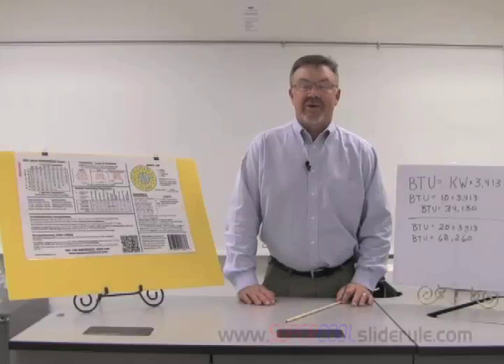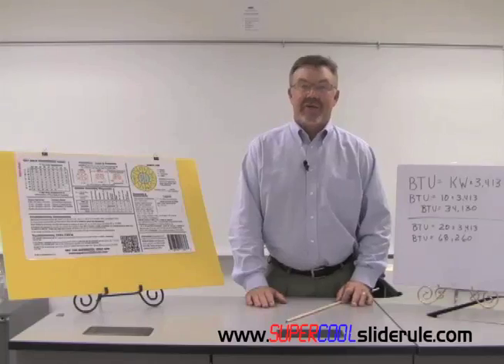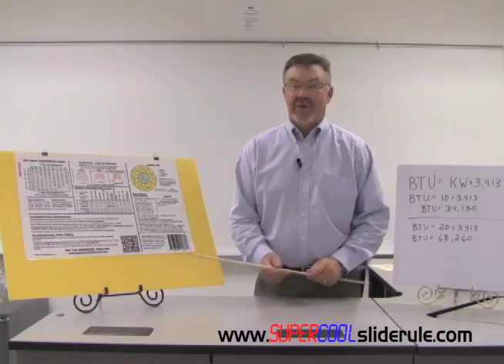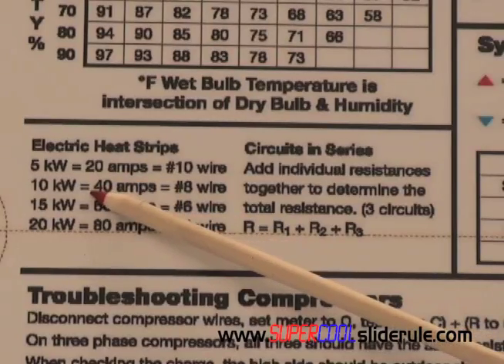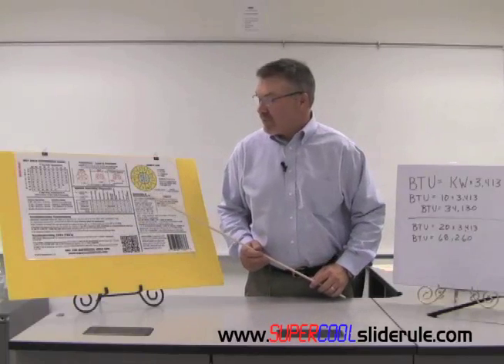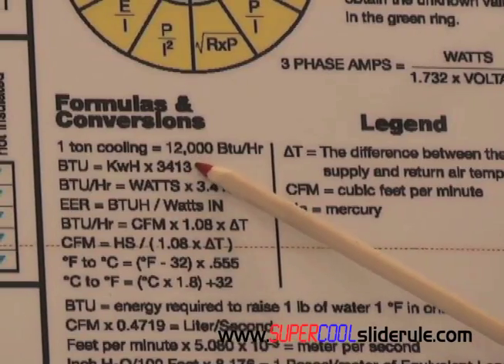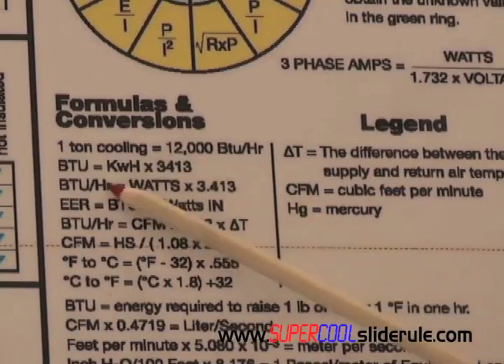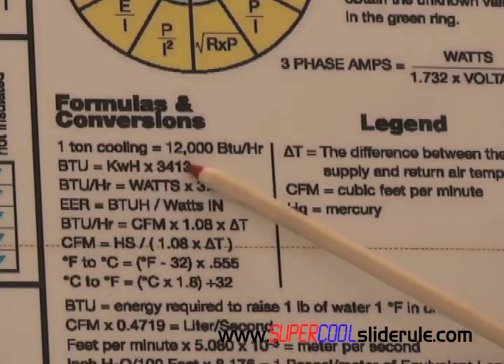This video is going to help you determine the BTU output of an electric heater. We're going to do two heaters. The first heater is going to be a 10KW electric heater. We come over to our formulas and conversions, go to the BTU output. We'll see that BTU equals KW times 3413.